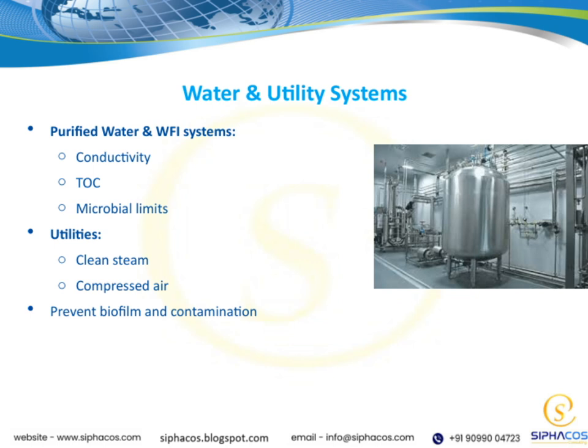Conductivity indicates the level of ions in the water, which reflects its purity. TOC, or total organic carbon, measures organic impurities that could affect product quality. Microbial limits are essential to prevent microbial growth that could compromise safety.